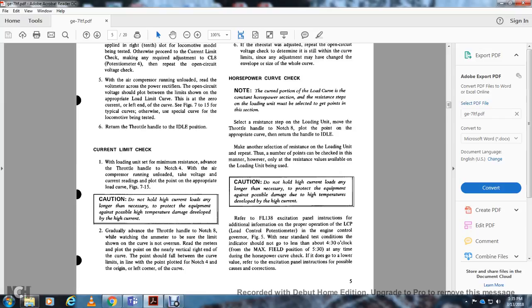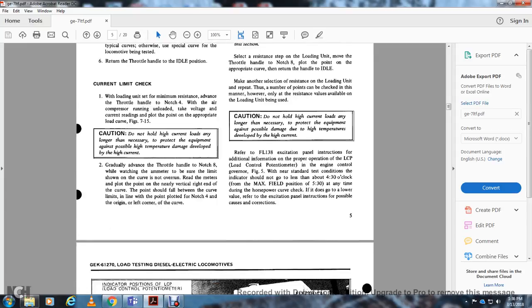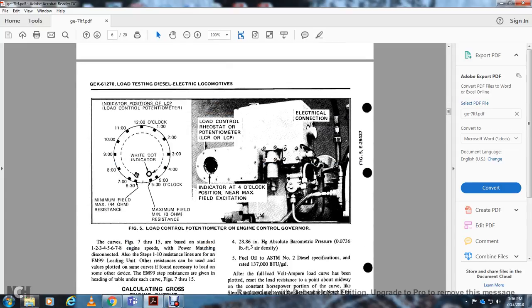Caution: do not hold the high current loads any longer than necessary, to protect the equipment against possible damage due to the high temperature developed by the high current. Refer to the field FL 138 excitation panel instruction for additional information. Proper operation of the load control potentiometer and the engine control governor, figure 5, is near standard under the test conditions. The indicator should not go below 4:30 o'clock, with maximum field position at 5:30 o'clock. If at any time during the horsepower curve check it goes lower than this, refer to the excitation panel instruction for possible corrections. Figure 5 shows the load control potentiometer and engine control governor.